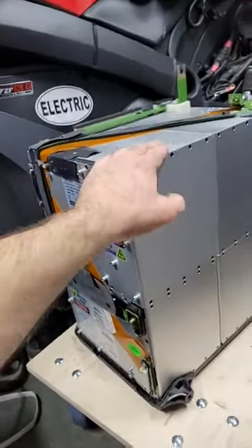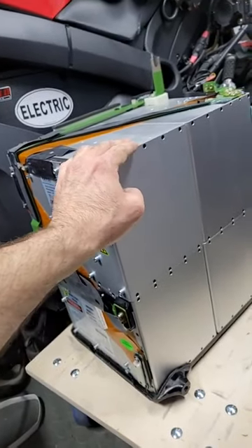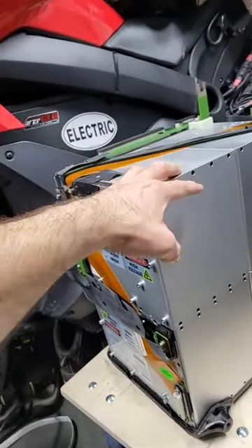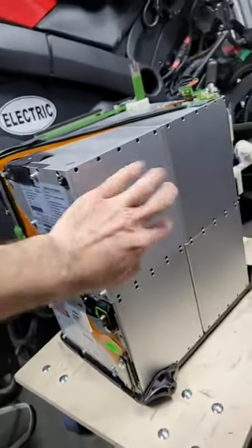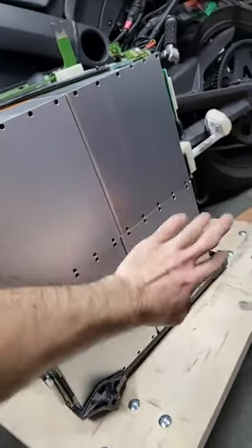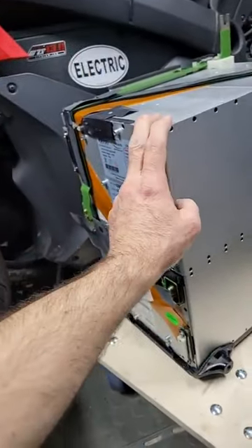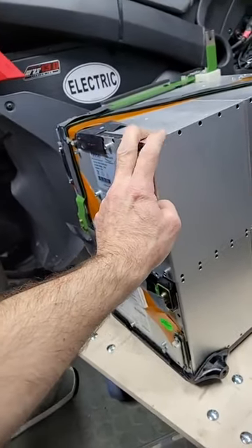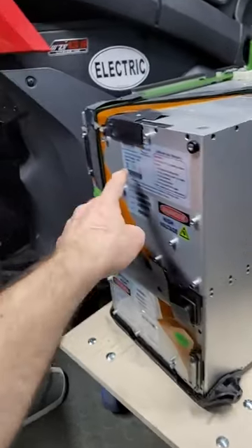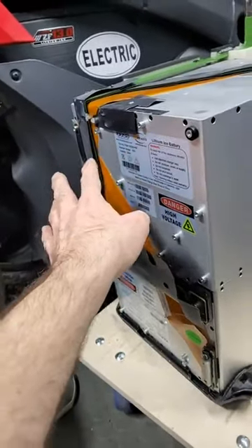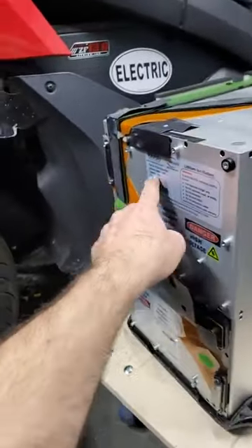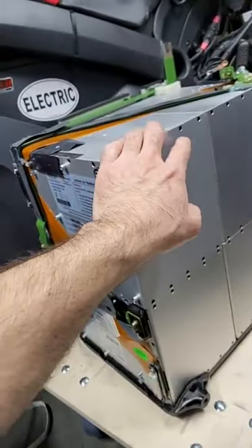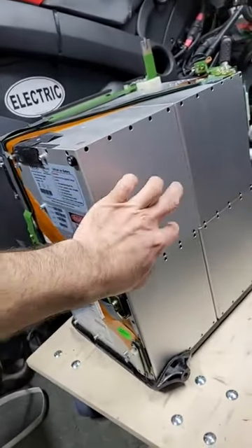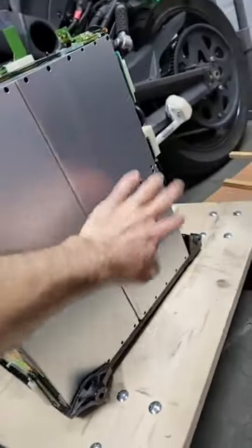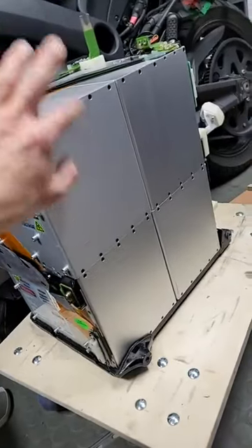Now with this battery they began with 11.4 kilowatt hours, which had 10 kilowatt hour usable. So each brick was 2.5 kilowatt hour. On this one it's normally 27 amp hour cells, but they indicated 25. I don't know exactly why, probably the usable capacity. Normally you will have 2.7 kilowatt hour per module here, per brick, if I can tell.